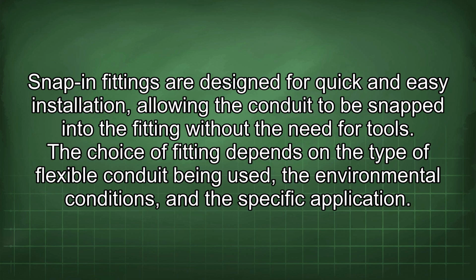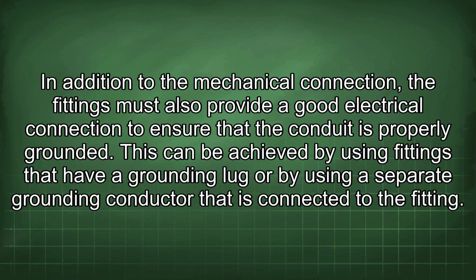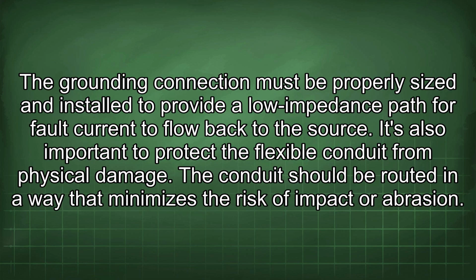The choice of fitting depends on the type of flexible conduit being used, the environmental conditions, and the specific application. In addition to the mechanical connection, the fittings must also provide a good electrical connection to ensure that the conduit is properly grounded. This can be achieved by using fittings that have a grounding lug or by using a separate grounding conductor that is connected to the fitting. The grounding connection must be properly sized and installed to provide a low impedance path for fault current to flow back to the source.